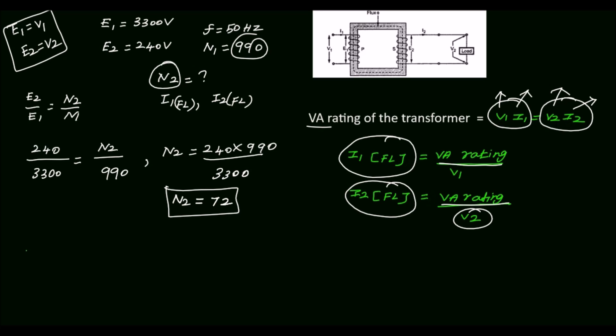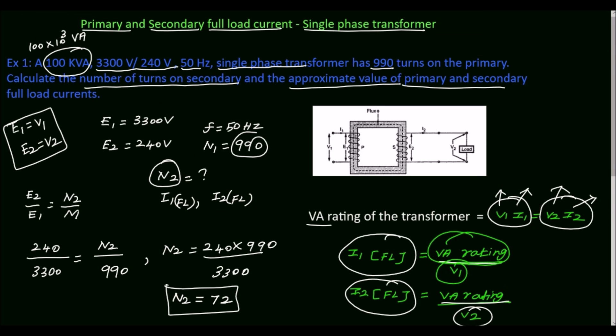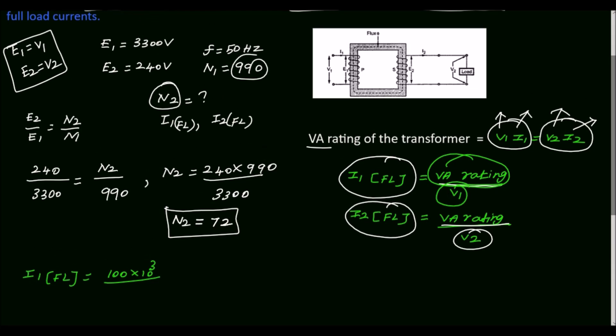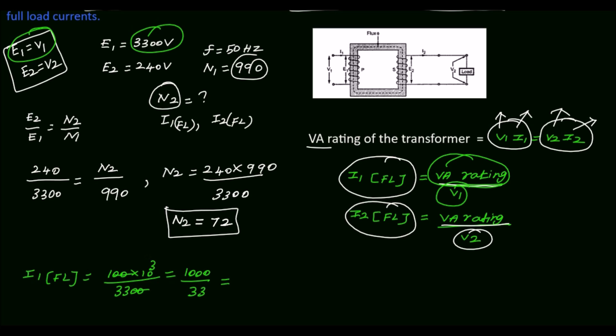Now we will calculate the primary full load current I1, which is equal to the VA rating of the transformer divided by V1. The VA rating is 100 into 10 to the power 3. For an ideal transformer, E1 equals V1, which equals 3300 volts. So I1 equals 100,000 divided by 3300, which equals 30.303 amperes. So the primary full load current is equal to 30.303 amperes.